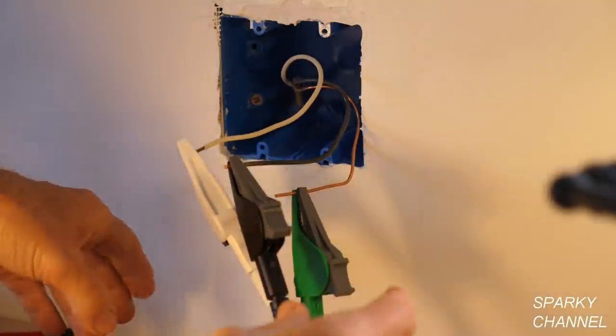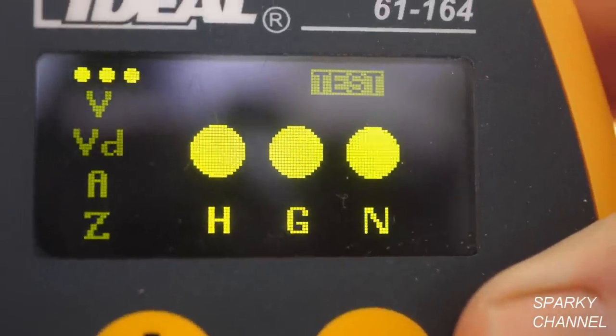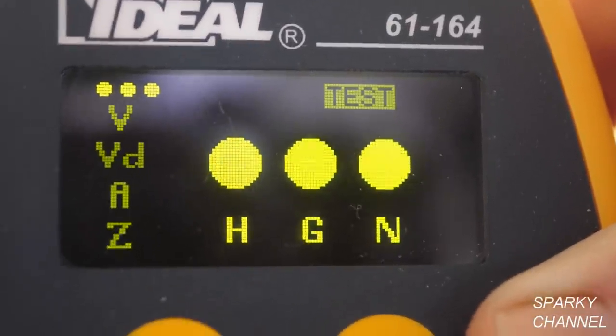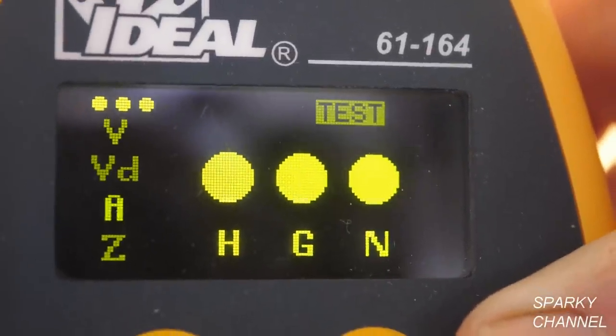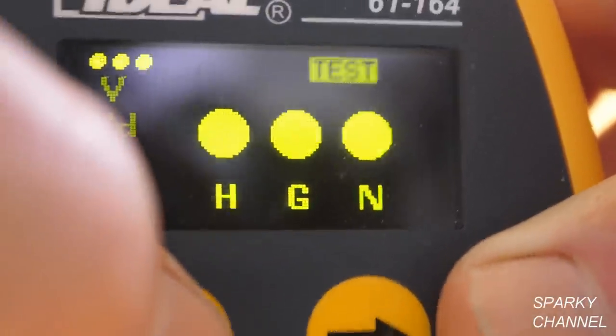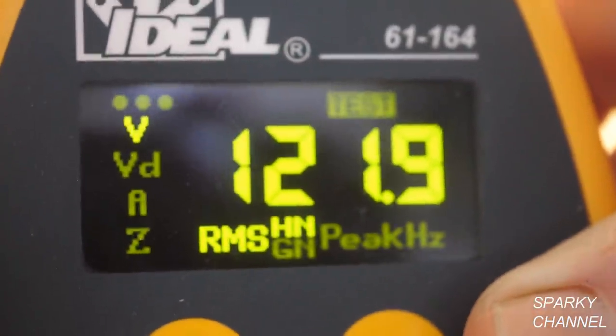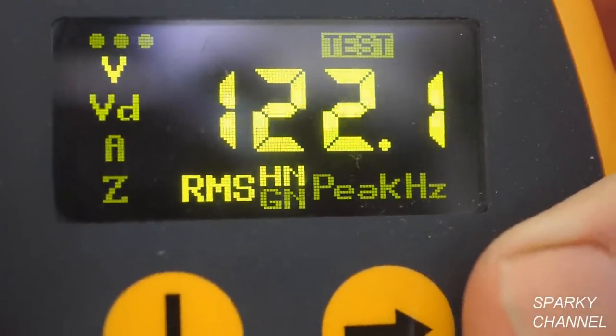And I'm going to go turn the circuit breaker on. So with the tester connectors connected to all three of the wires, we see that the hot, the ground, and the neutral are all good because the lights light up. And we press the button down one and we have 121.9 volts AC, which is excellent. It's a good strong voltage.